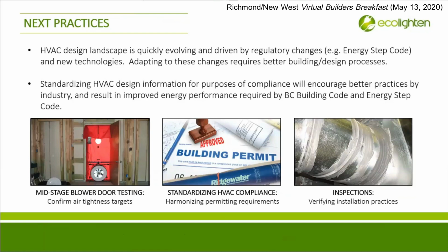This means more and better training. Governments will need to adopt best practices as a compliance requirement, which means establishing a standard and enforcing it. Load calculations and system designs upfront before building permit, installation inspections, and blower door tests before cover-up, and commissioning verification before occupancy. And all this harmonized so that the rules are the same from one authority having jurisdiction to the next, which is not the case now. From one city to another, the rules are different.